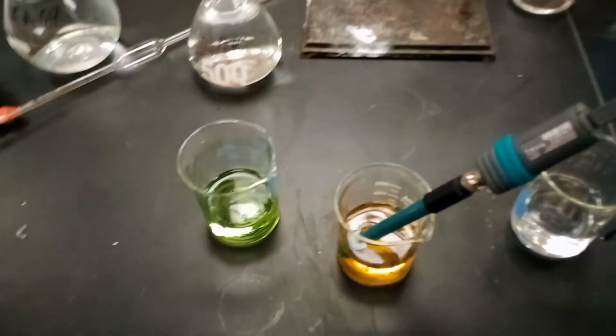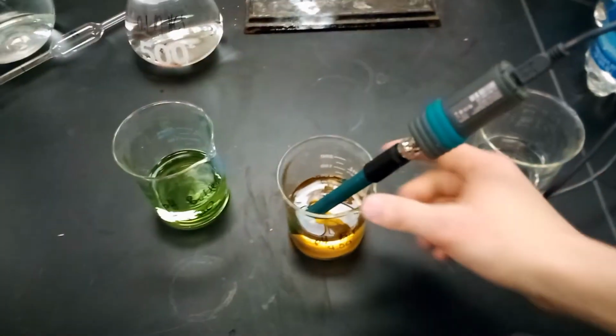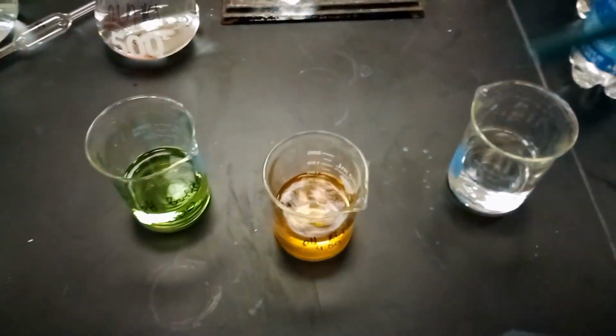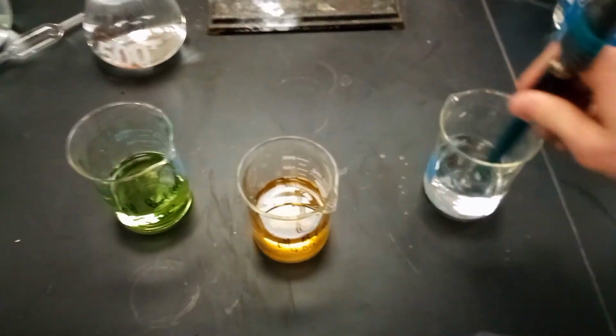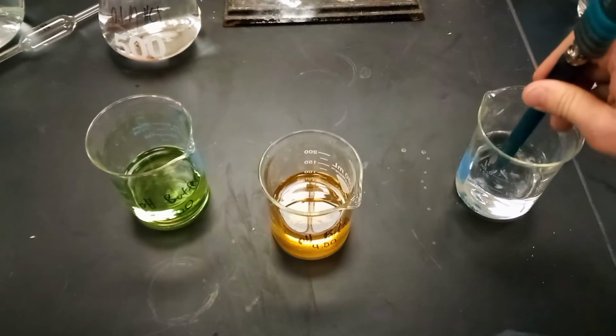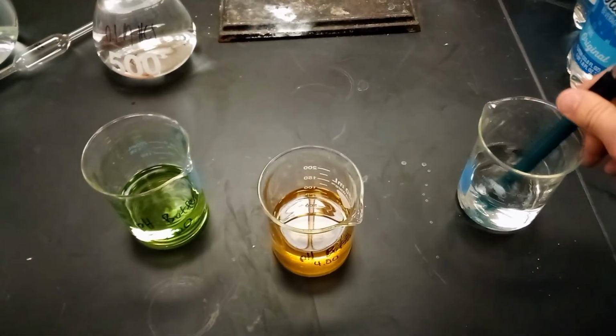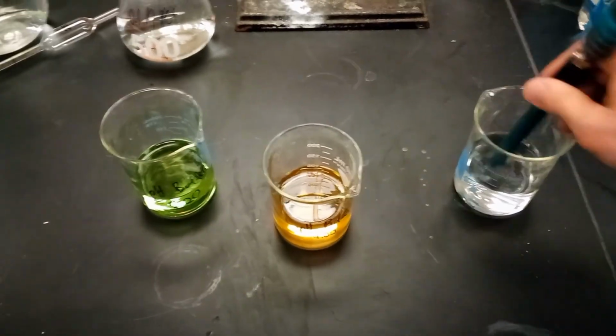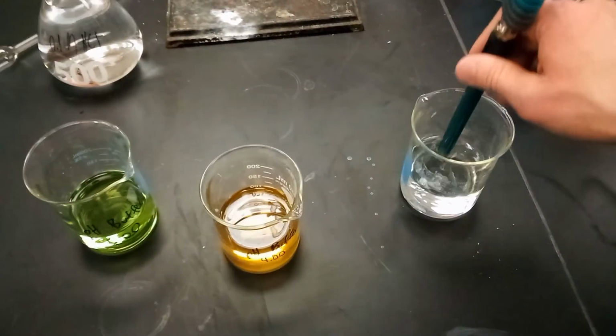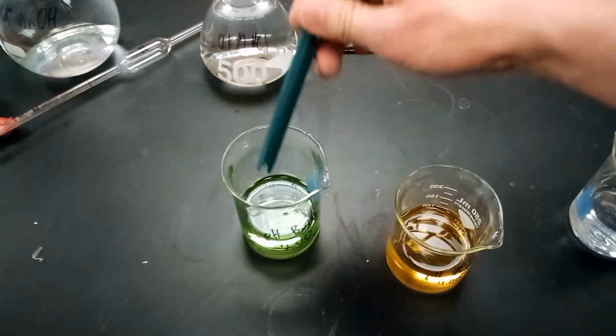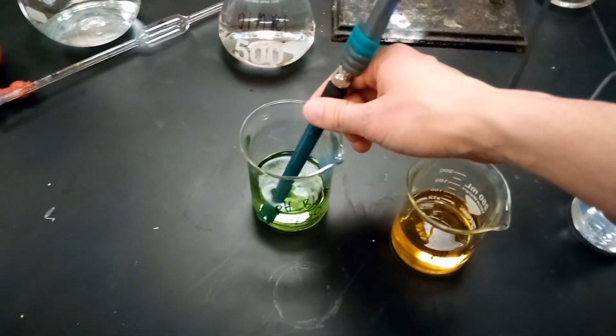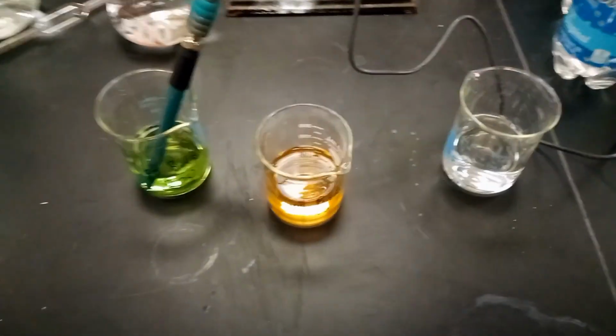So we'll move the electrode back into the distilled water to clean it off, essentially, like so. Carefully rinsing it so that we don't mess up the buffer systems. Okay, now that it's thoroughly rinsed and cleaned, we can add it to the buffer of 7.00, like so.